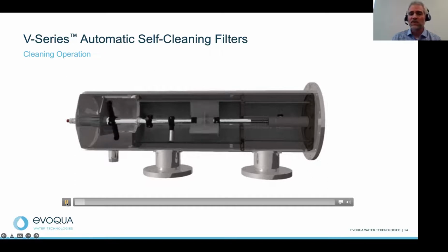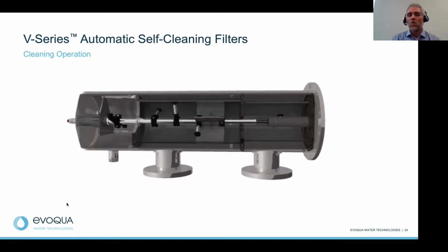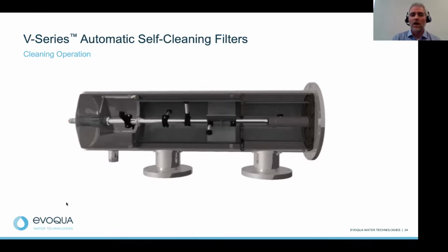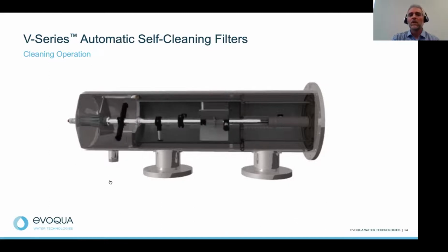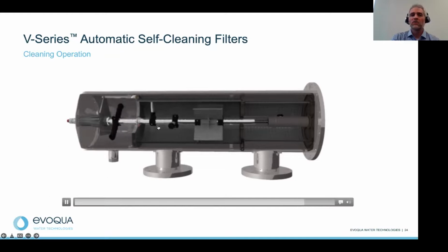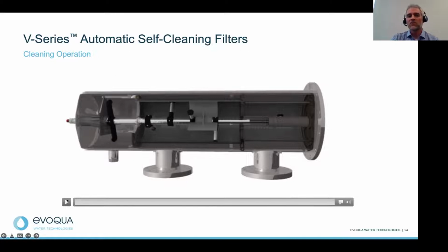Again, this is just the cleaning cycle. So when you're filtering, none of this is moving. But when you are in an active cleaning mode, this is what's happening, right? Suction valve or flush valve is opened. You have flow from the high pressure zone to the low pressure zone, removing that dirt and debris.